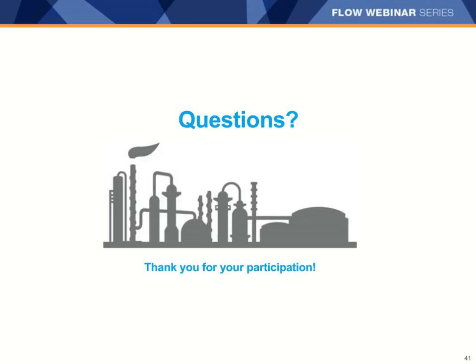A question, would it be accurate to say that the accuracy of the volume of oil calculated, or the net oil, I believe, is just as dependent on the input oil and water density values as the bulk density calculation done by the meter? Absolutely, your net oil accuracy is incredibly dependent on the accuracy of the input oil density and water density. That is probably one of the biggest challenges with using a density-based net oil computer that we've seen in our Series 3000 and in the PVR application itself, is just getting that oil density and water density correct and correctly input at standard temperature.